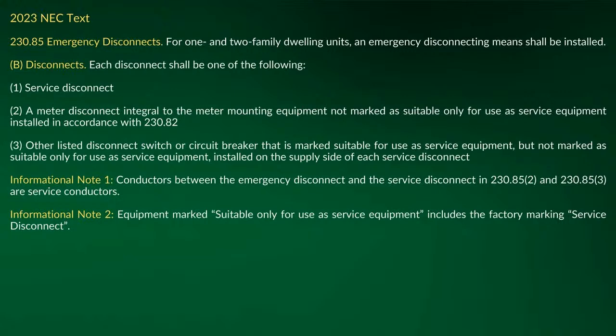Yeah, well, I look at it, first of all, you're not going to create two different grounding electrode systems. I'm just going to nix that right now. I agree. Now, are you going to put an overcurrent protection device out there? And if you put that overcurrent protection device out there, you're not going to ground at that spot. You're just going to have overcurrent protection with a disconnect. You see what I'm saying?